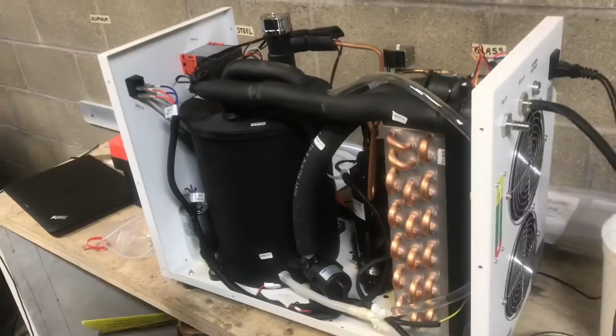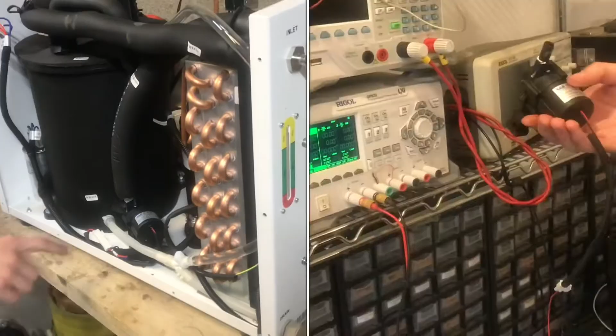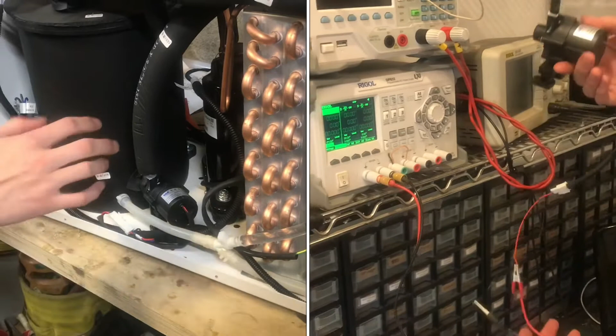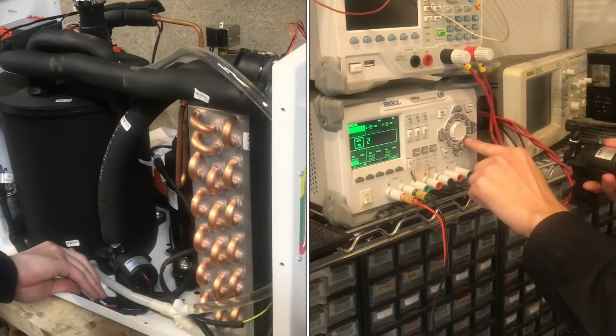Now the reason we know this motor is bad is because whenever I plug it in and turn on the unit, the temperature control module has no display and no error code. That's not normal. What's actually happening is there's a short circuit on the 24 volt circuit, which is dropping the voltage enough that it's not getting enough power to even turn on.